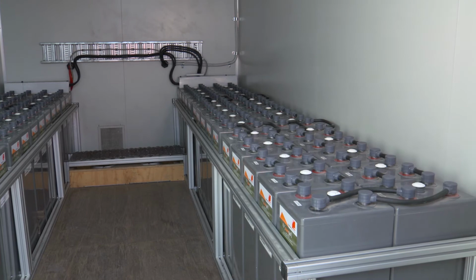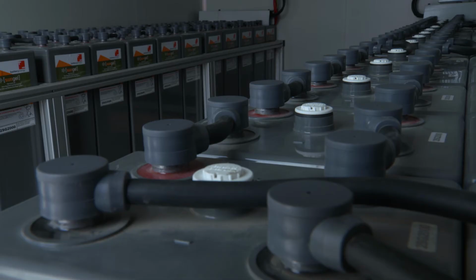Through a fair bit of engineering, we loaded the system here at site and we tuned it and tuned it. Now, anything above that 80 amp per phase load for the brewery, we supply out of batteries. As soon as the load decreases, we take that extra out of the capacity of the supply and charge the batteries up.